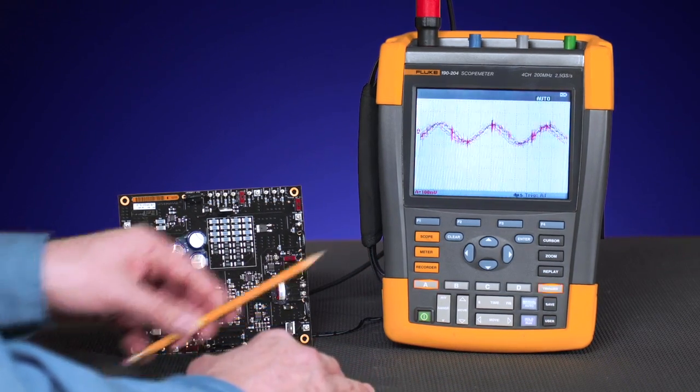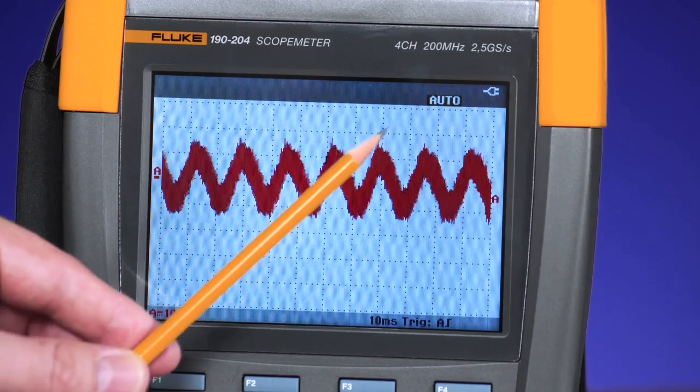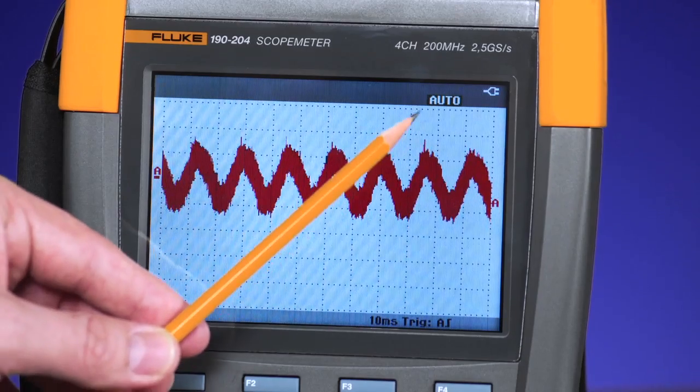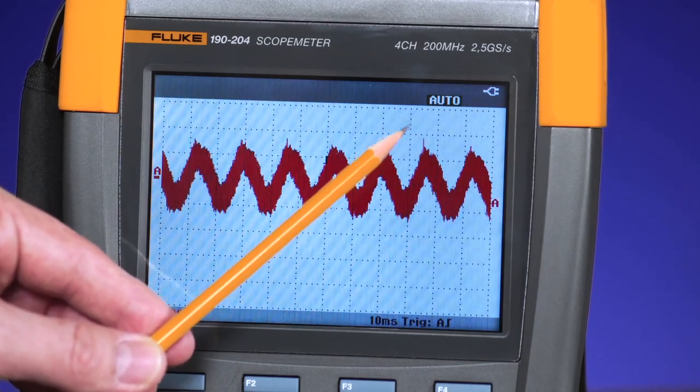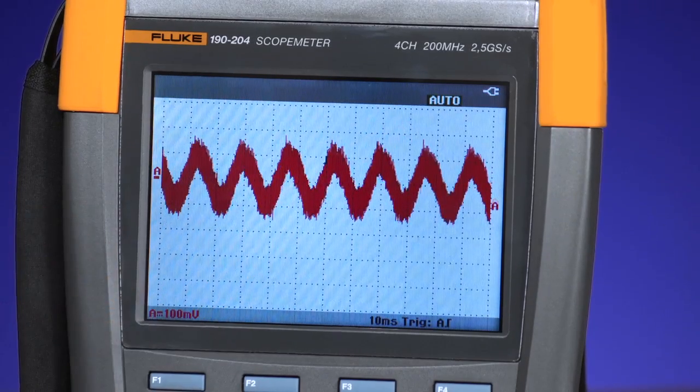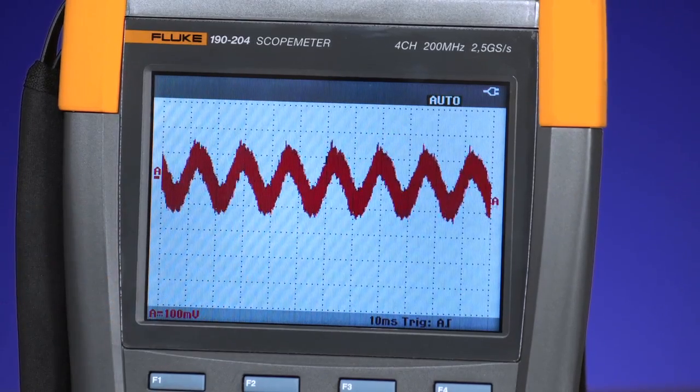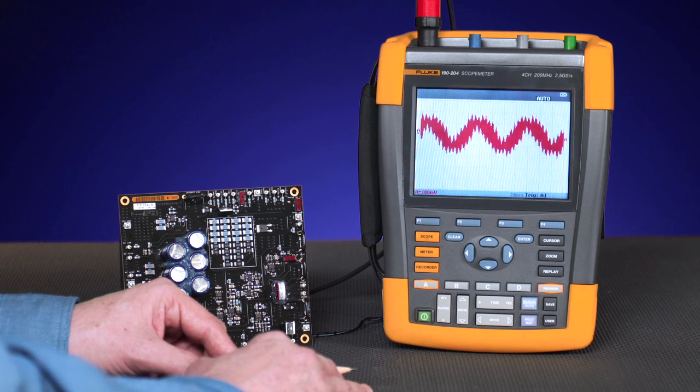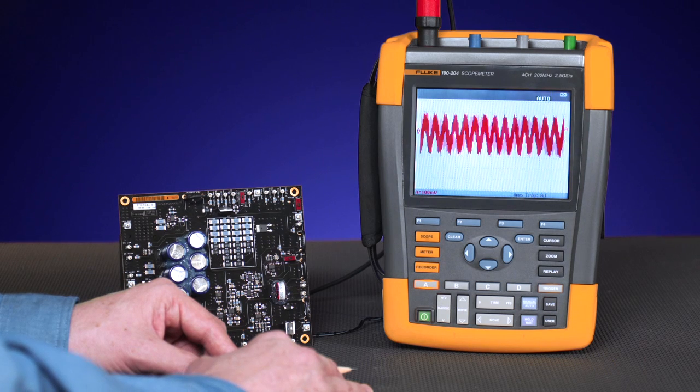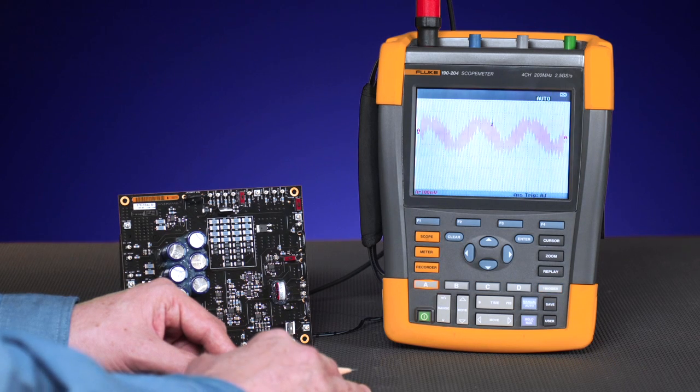We do this to make sure we're in the auto-connect and view mode, which will allow us to move quickly from test point to test point to acquire waveforms and display them on the screen.